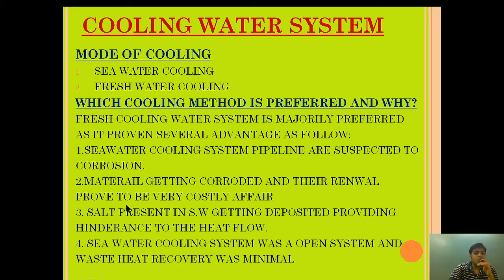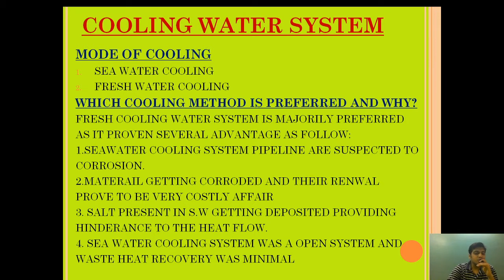Also, the salt present in seawater — mainly sodium chloride — gets deposited in the system at elevated temperatures, causing scale formation that creates hindrance to heat flow, resulting in inefficient heat transfer. This was a major problem with the seawater cooling system.